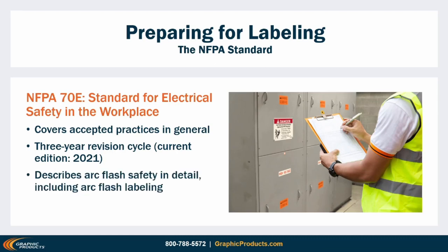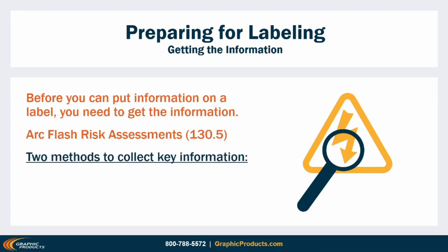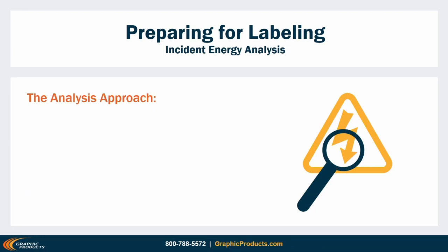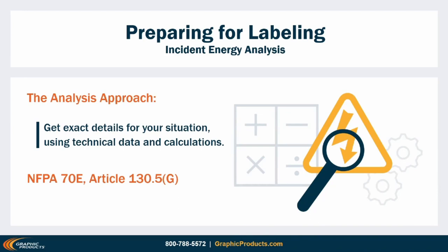NFPA 70E dedicates a lot of its content to arc flash safety. It requires arc flash labels to include certain specific details that will inform safe choices when workers need to interact with the equipment. But before you can put detailed information on a label, you need to get that information from somewhere. Collecting that information is part of an arc flash risk assessment described in Article 130.5. Within that process, there's an important section for identifying what PPE is really needed, offering two different methods: analysis and categories.